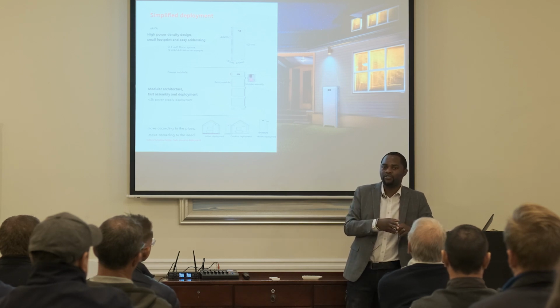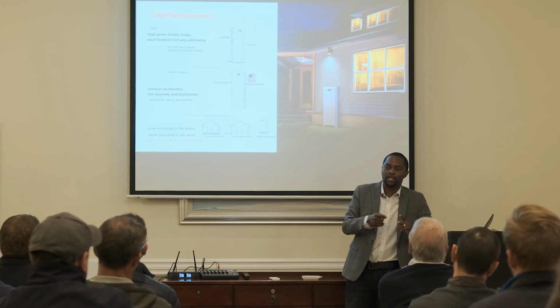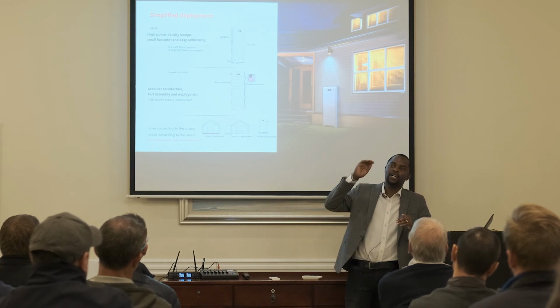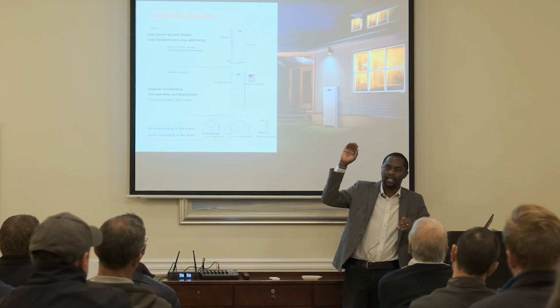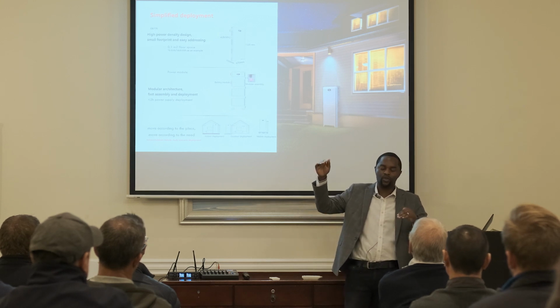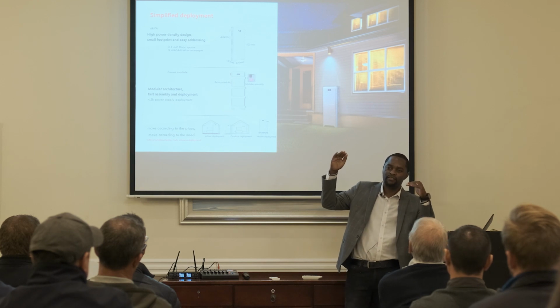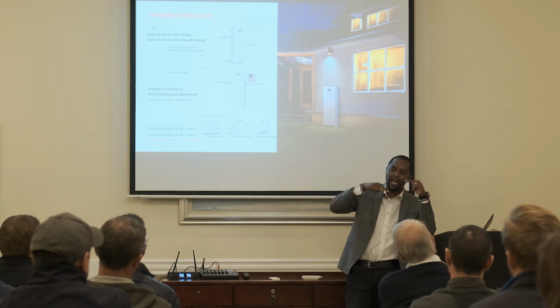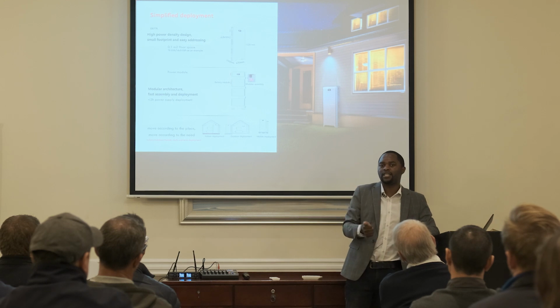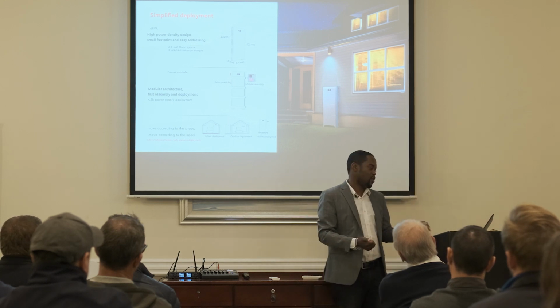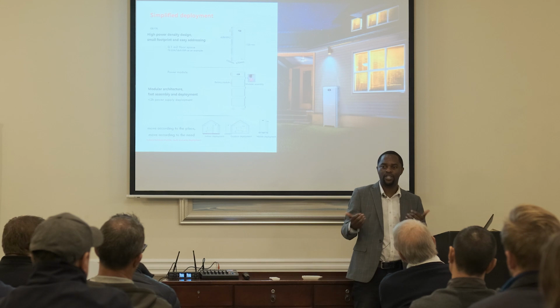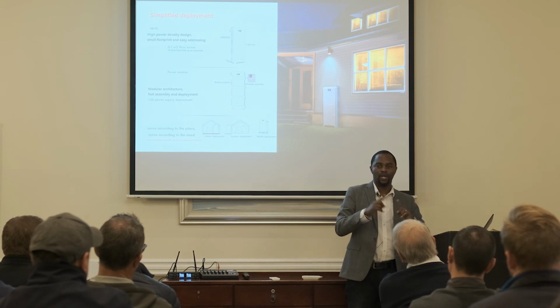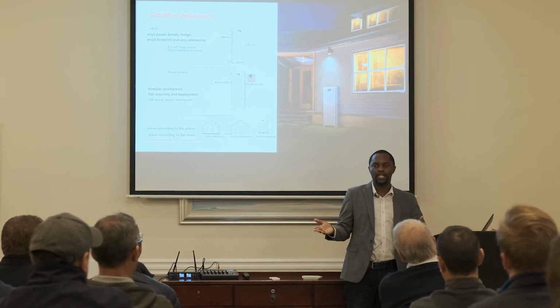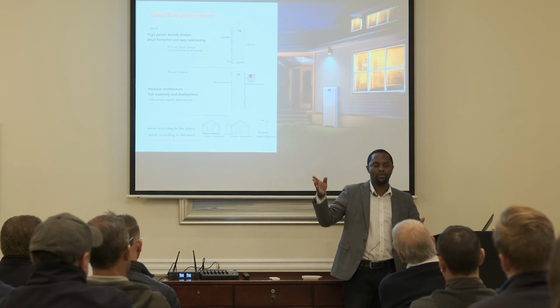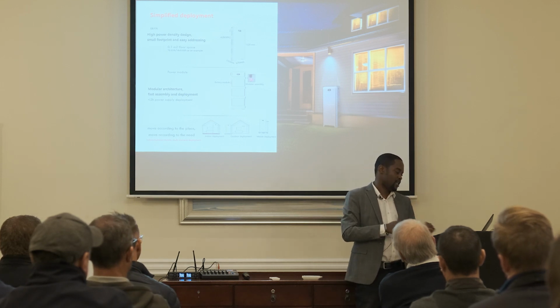If you bond on the output, if you bond your neutral and your earth, you can actually end up tripping your earth leakage, because now the grid bond that Eskom provided on the transformer, and your bond, become two different bonds. If they are at different potential, there will be a current flow. That current flow can be detected by the earth leakage, then it trips. So you need one bond at a time. So when you've got Eskom, don't worry about the bond. Your relay should be normally open. The moment you lose the grid, you have lost that transformer bonding. That's the only time you need that relay to close.